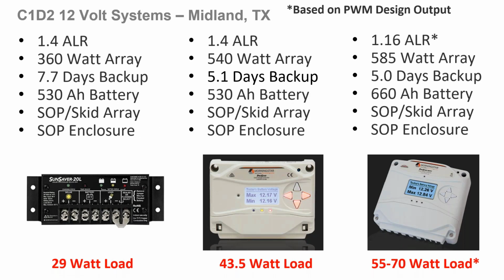Okay. So looking at these three controllers for a 12-volt system, Midland, Texas, you've got the Sunsaver 20L 12 volt on the left-hand side, and we're saying that's going to run at maximum about a 29-watt continuous load. Going through what that system is, it's about a 360-watt array using 180-watt solar modules. It's got a 530 amp hour battery bank for 7.7 days of autonomy, which is a little bit on the high end. And you'll see the array is either going to be side-of-pole or skid mounted with a side-of-pole enclosure. Moving on to the ProStar PWM, we've now got a 1.4 ALR, 540 watt array, 5.1 days of backup with a 530 amp hour battery, side-of-pole skid array, side-of-pole enclosure, now supporting a 43.5 watt load.